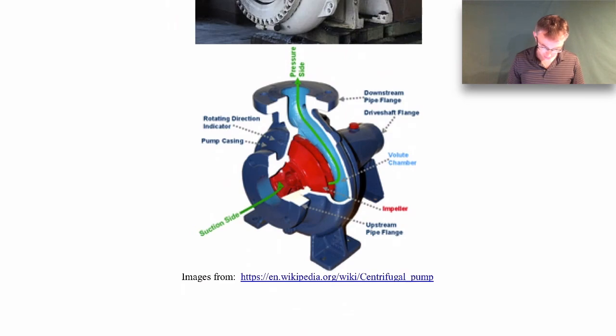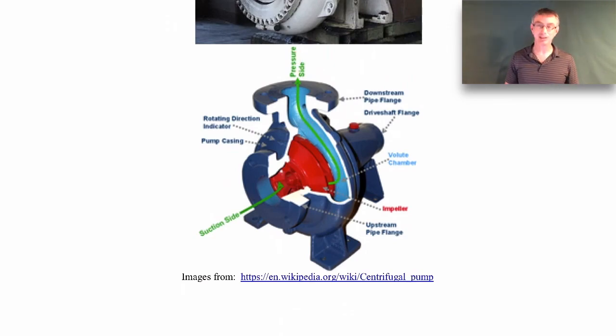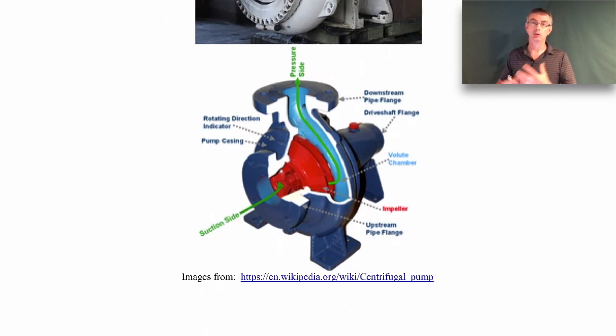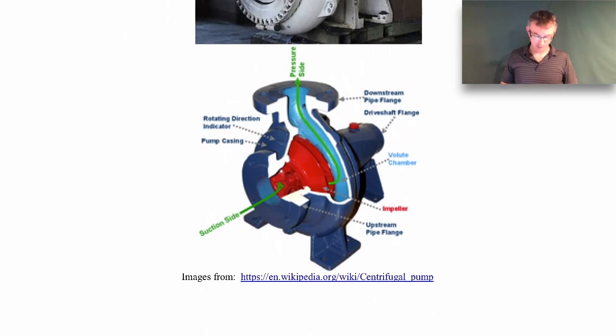This is called a closed impeller because there's a shroud on the front and the back, so the fluid comes out through a gap in the middle. It gets thrown out to the side and collects in the volute — the blue chamber. The high-speed kinetic energy of the water being thrown outward gets converted into pressure as it slows. The area also increases through the volute, and from Bernoulli's equation that produces additional pressure, so you end up with a high pressure going out.